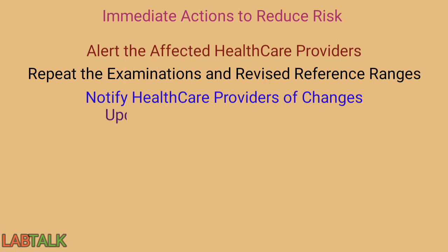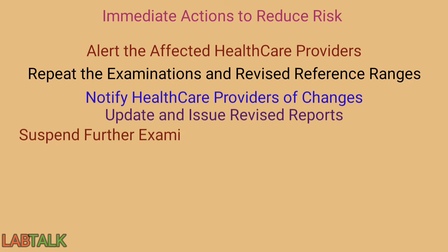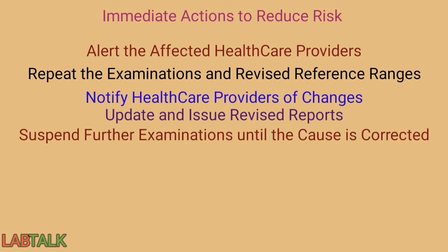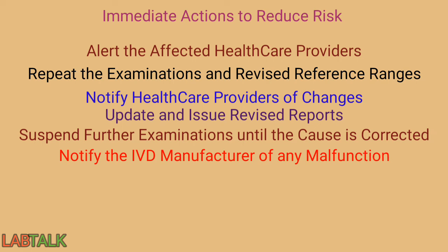After that, update and issue revised reference ranges and suspend further examination until the cause is corrected. Another type of immediate action is to notify the IVD manufacturer of any clinically significant malfunction, use error or deficiency in IVD device design or labeling.